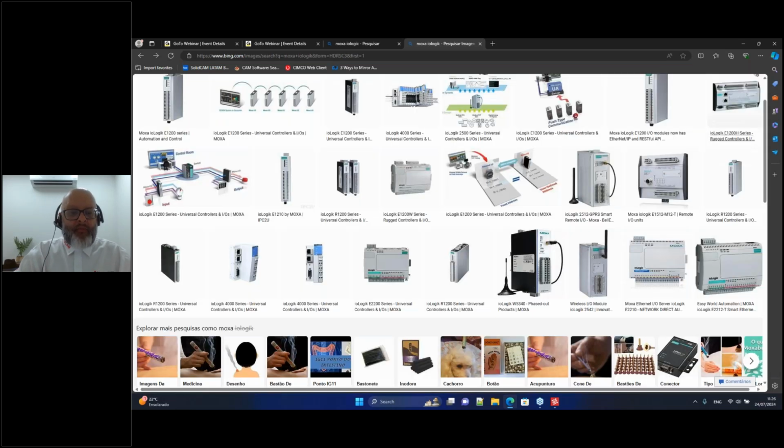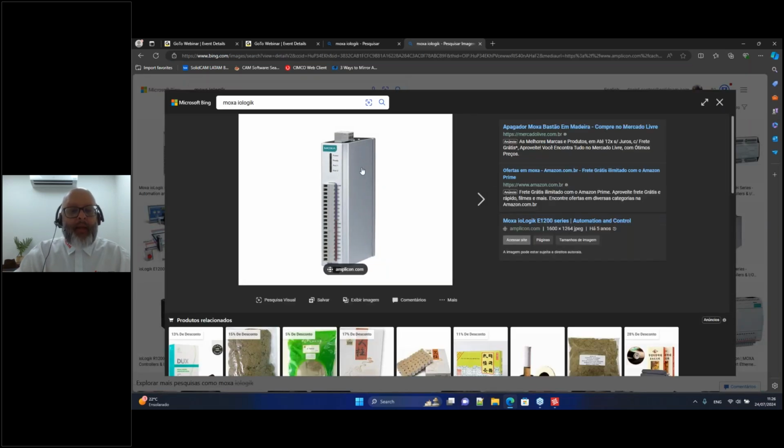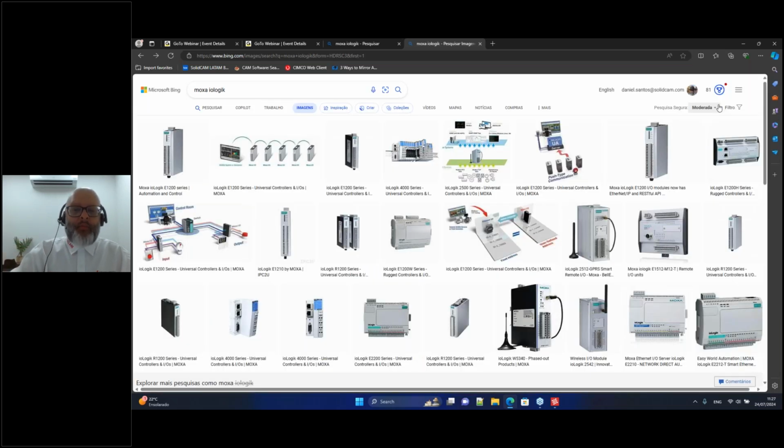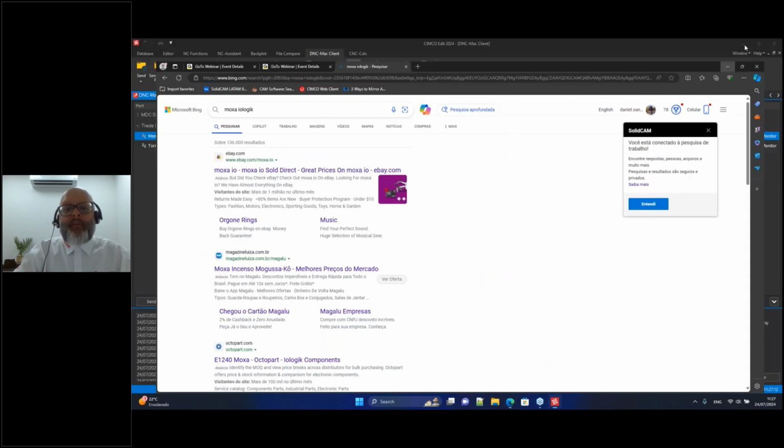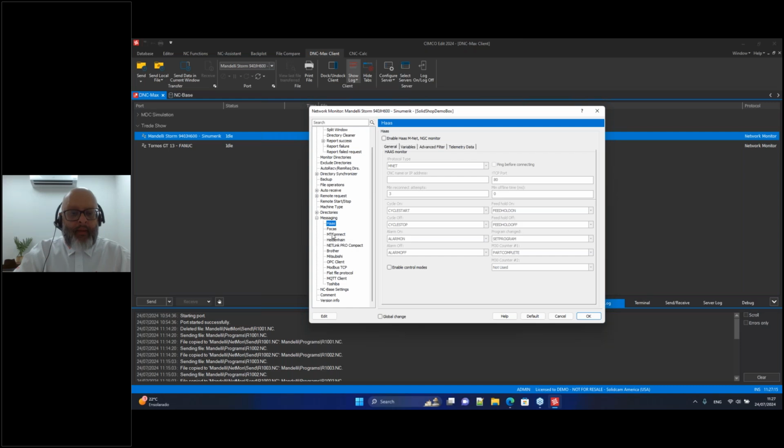You can get up to 64. Most people start with 16. You put equipment like that on the machine, collect the electrical signals from the PLC, connect them to one of these ports, and then you can read the signals through an Ethernet port. CIMCO can also work with very, very old machines, 20, 30, 40 years old. You can monitor one way or another, but it's not the best way. The best way is, if you can, to do this through Ethernet.